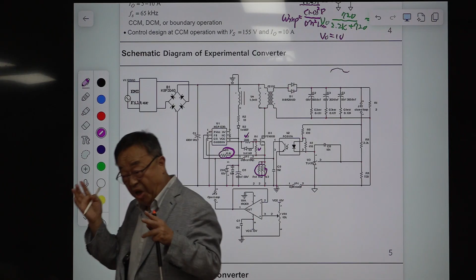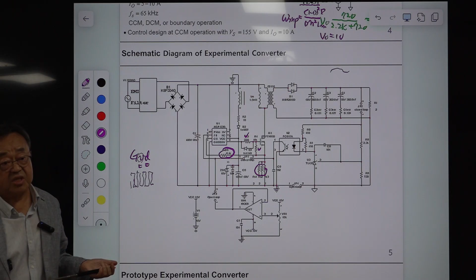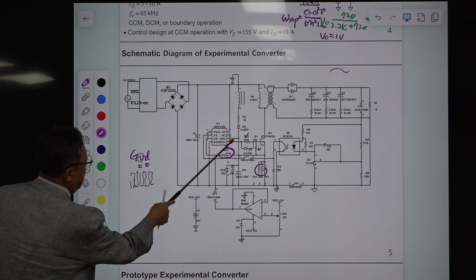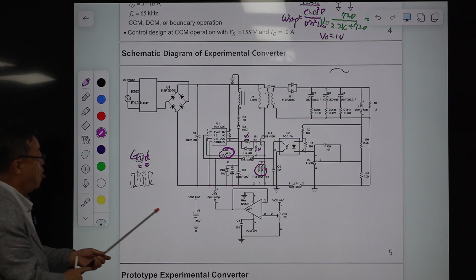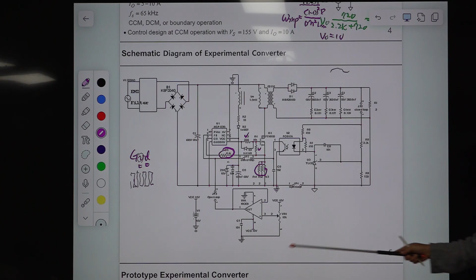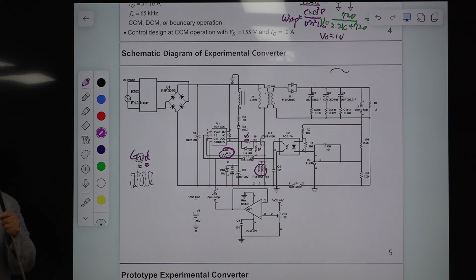But in measurement, you need to deal with the digital signal at the input and the analog signal at the output. So the alternative way is measuring this control voltage, which goes to this modulator. So you don't measure this; the gate drive signal is in the loop. Measure input and output, and you extract this information. For that purpose we are measuring this. This is an additional op-amp to implement the unity gain buffer, and we have an additional power supply to provide the power here, but this is unnecessary. There are several junctions here. You connect the jumper cable, disconnect the jumper cable, then you can do the measurement or normal operation of this converter.